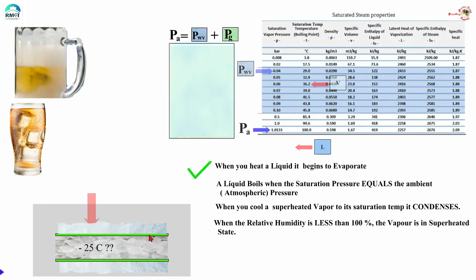condensation business, let us now come back to our fridge compressor. We saw that our desired mean temperature is minus 20. For this mean temperature to be minus 20, we also saw that the temperature of the freon is going to be at least minus 25. And by the time this freon is coming out of the evaporator in a superheated state, the temperature is still desired to be minus 20, because the freon is evaporating at say minus 25 and then getting superheated by 5 degrees. So something like minus 20 is the temperature of freon if everything is working all right.